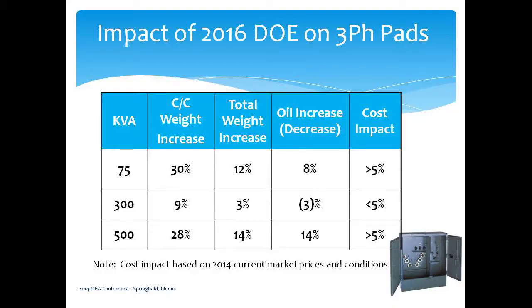What we are seeing is kind of unique: by keeping the size of the tank down, which you can do because the overall heat is less for some of the three-phase units, it still nevertheless increases the weight of them, in some cases very considerably. The weight of this one, in particular, is 500 kVA, going up 14%. And I'll show you some of the actual numbers on that too, so you'll get a feel for it.